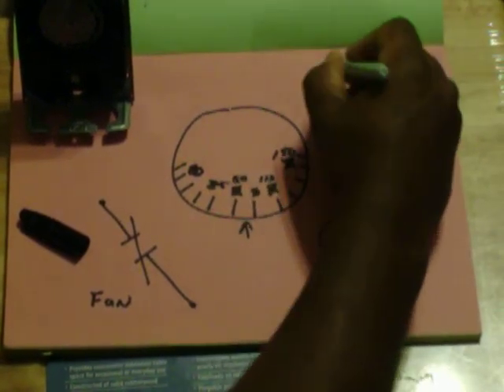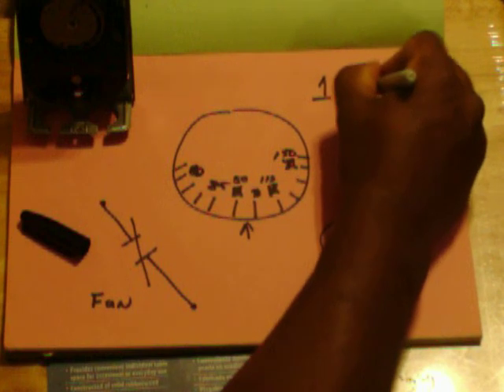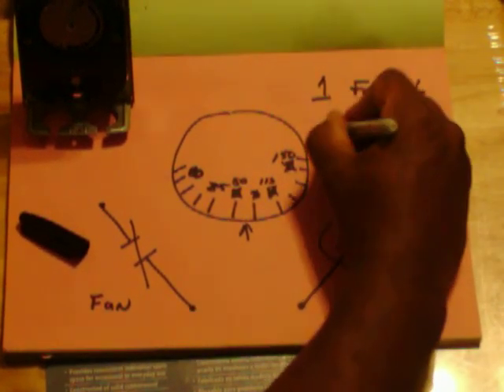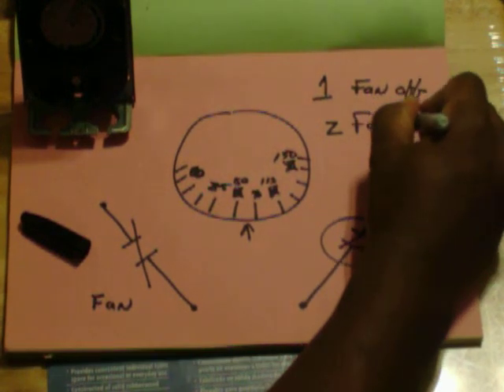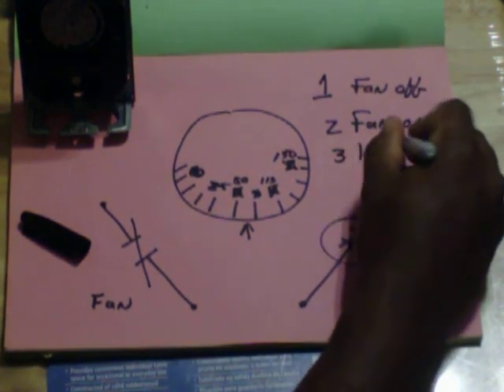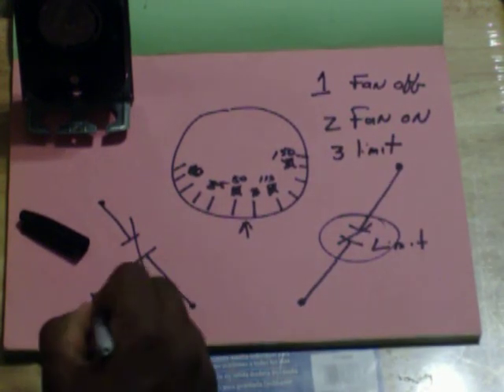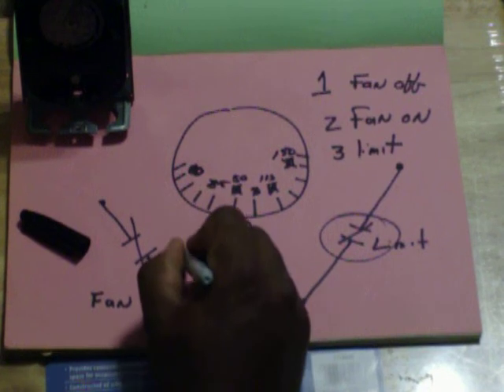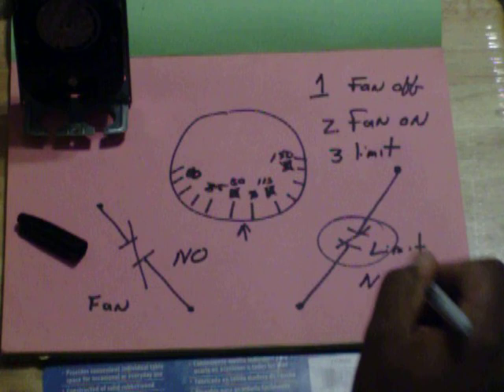Pretty simple device, it's just an old mechanical device. We just need to remember these pins in order. The first one, number one pin, is your fan off. Two, fan on. Three, is your limit. Remember that your fan switch is normally open. Your limit switch is normally closed.